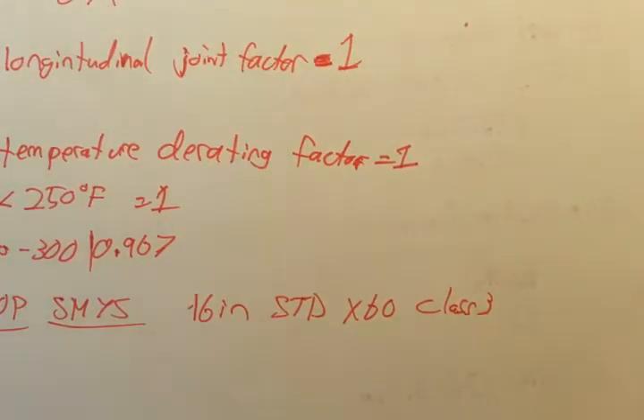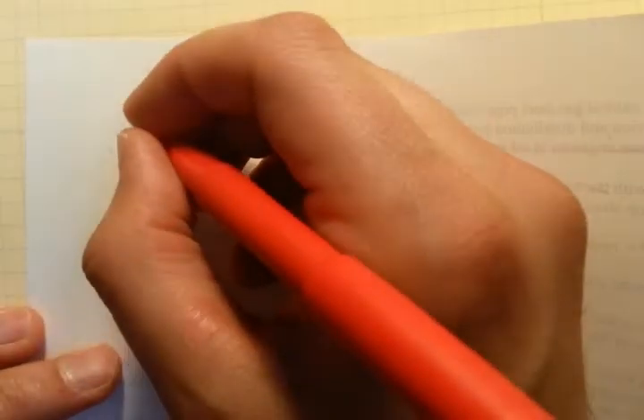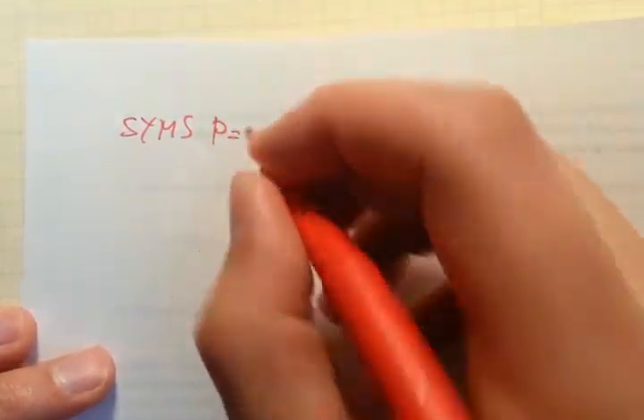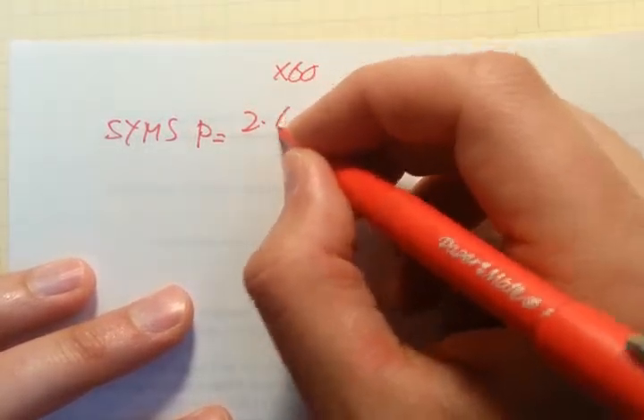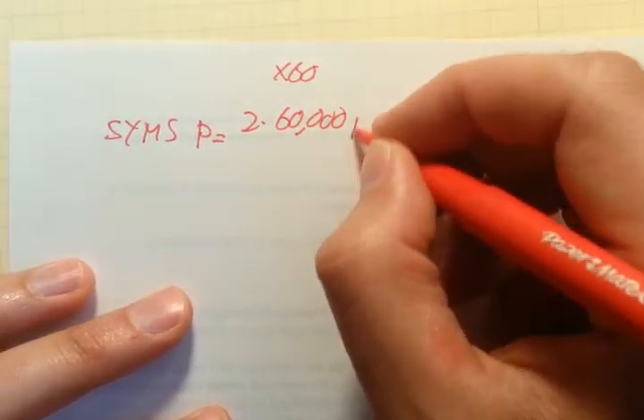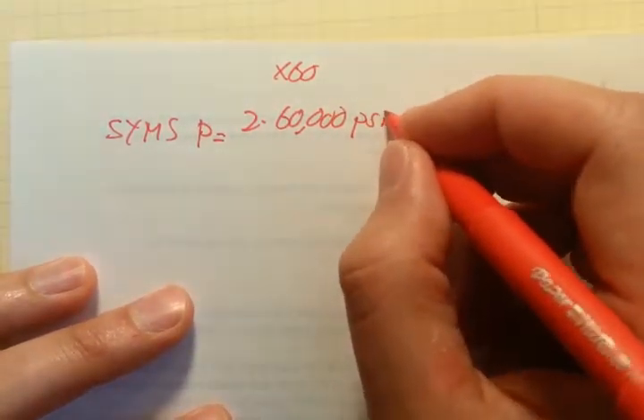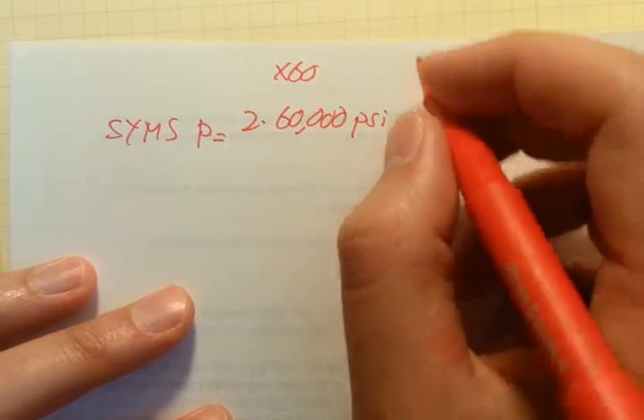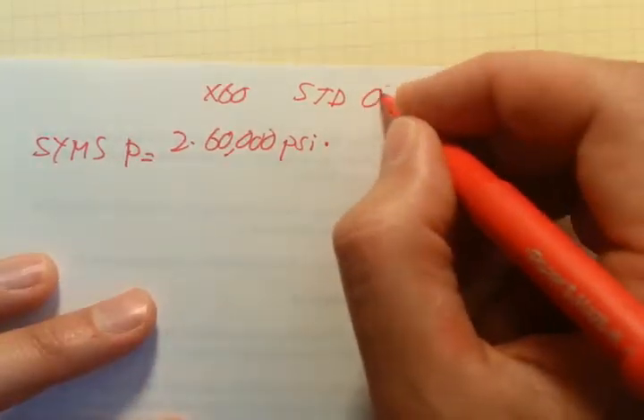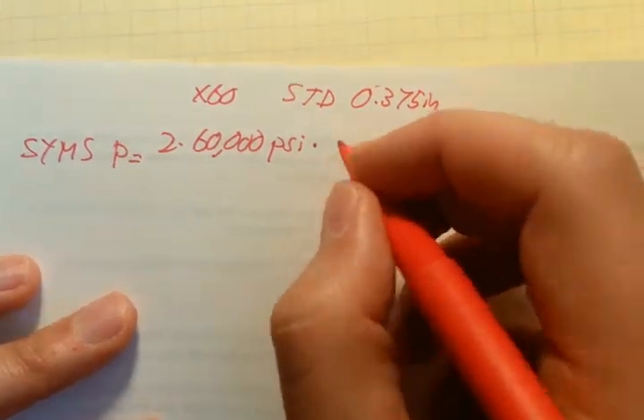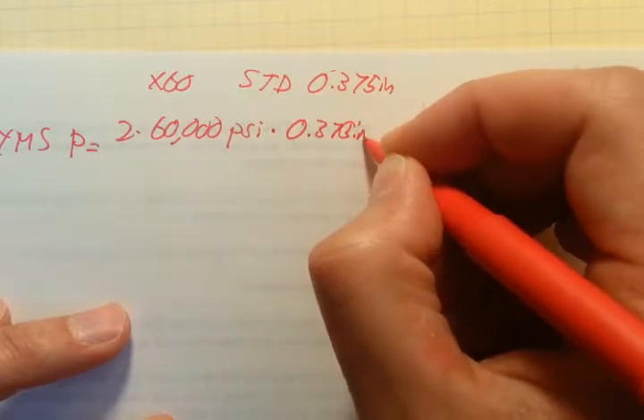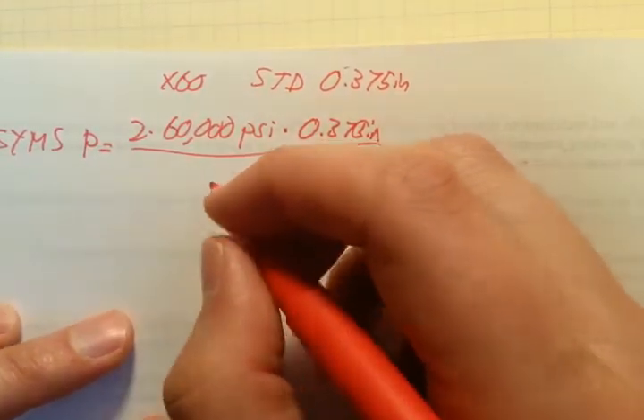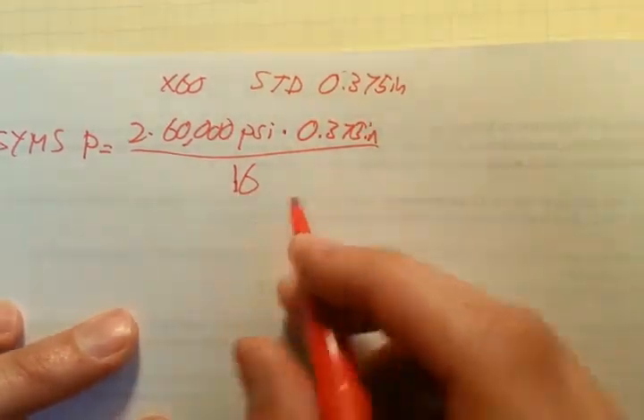Let's find the yield pressure first. That's going to be 2 times the X60, which is 60,000 PSI, times the wall thickness—standard wall thickness for 16 inch pipe is 0.375 inches—and all that over, in this case the size and outer diameter are the same, so just over 16.